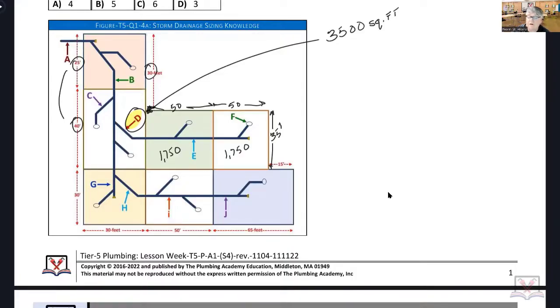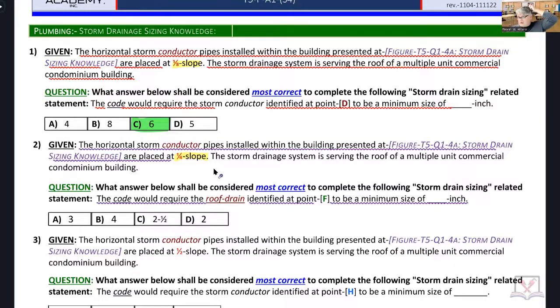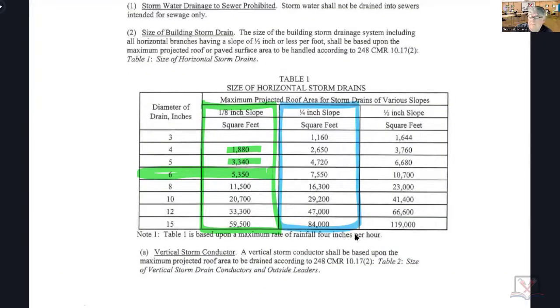If you were in this building, you would do everything either in an eighth-inch slope or a quarter-inch slope. But when you get questions, they're treating it as individual questions for an individual building, even though they look exactly the same. Quarter-inch slope, what is the constant? That's the column you're going to be in. There's quarter-inch slope, also represented by 250. 250 square feet of roof area can drain through a one-inch pipe in one hour. I don't care whether it's copper or steel, it's just an engineered constant.